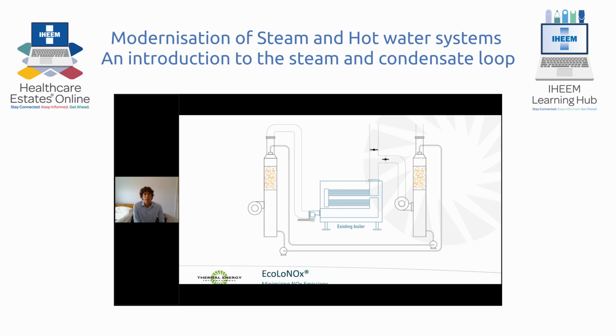Thermal NOx occurs in combustion processes where the flame temperature is above 1300 degrees C. This is the highest temperature part of the flame. Many combustion strategies to reduce NOx involve increasing the thermal mass of the combustion air by recirculating exhaust gases. Effectively, by recirculating these inert gases, they add more combustion gases and lower the flame temperature.